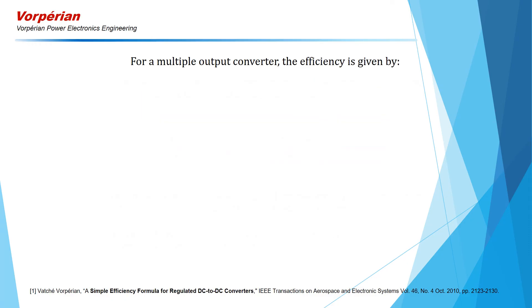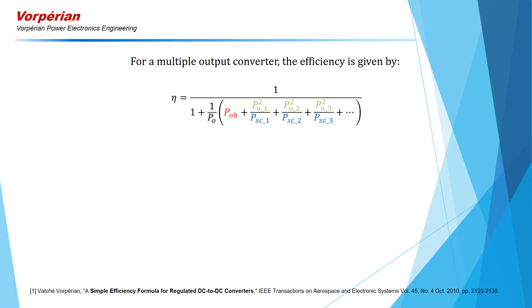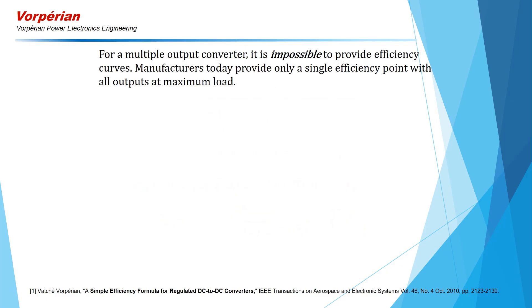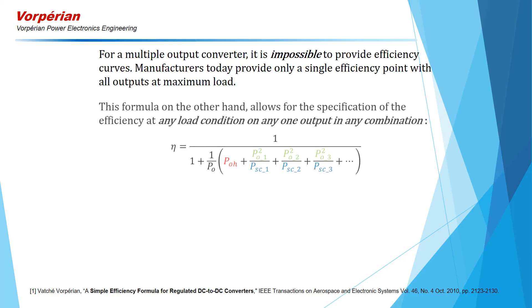For a multiple output converter, the efficiency is given by the following formula. In this formula, PO is the sum of all output powers — PO1, PO2, PO3, etc. POH is the measured input power at no load on all outputs. PSC is defined for each individual output at maximum power on that output, while the power on all other outputs is zero. For a multiple output converter, it is impossible to provide efficiency curves, and manufacturers today provide only a single efficiency point with all outputs at maximum load. This formula, on the other hand, allows for the specification of the efficiency at any load condition on any one output in any combination.